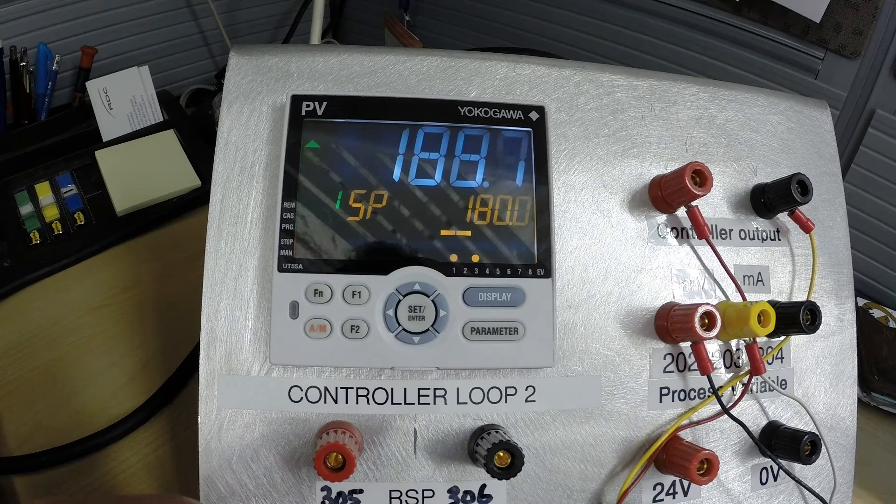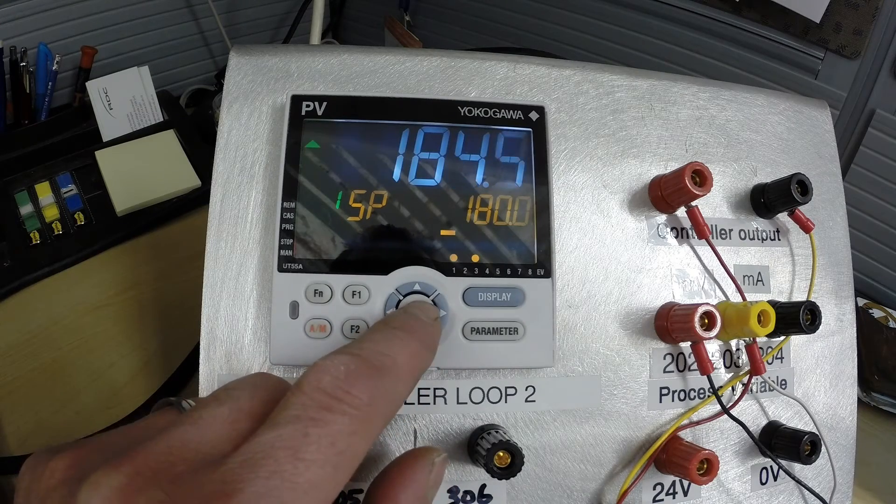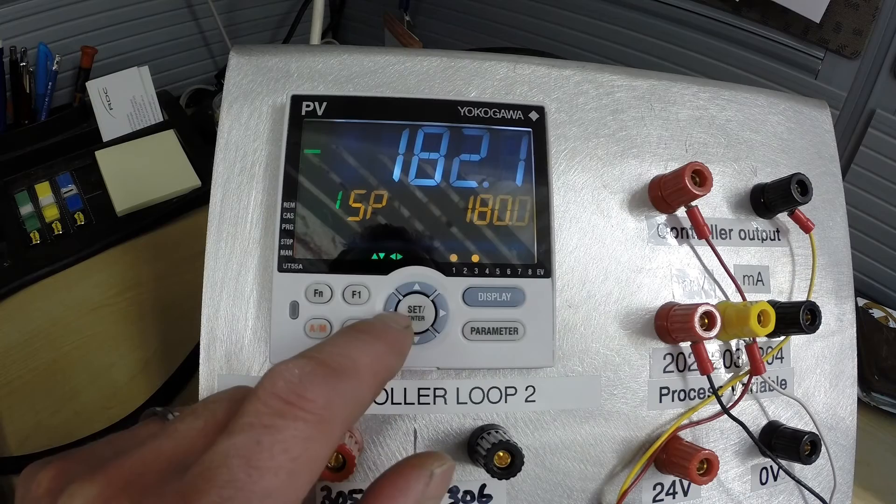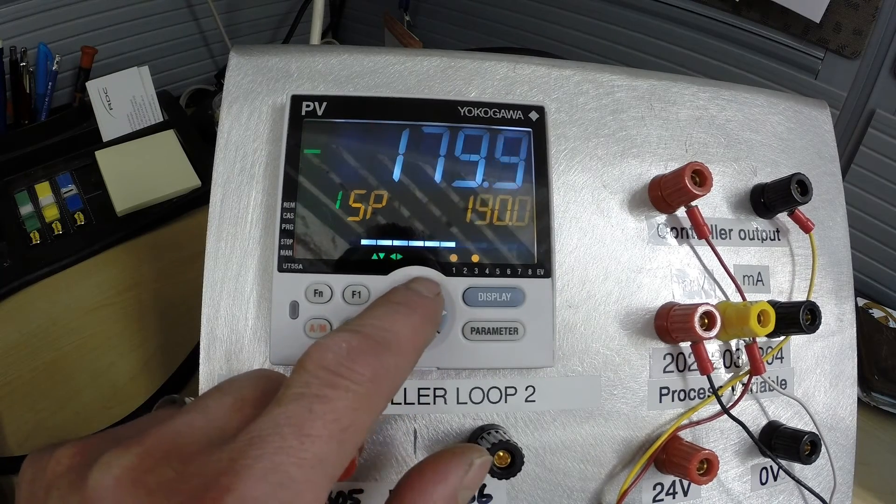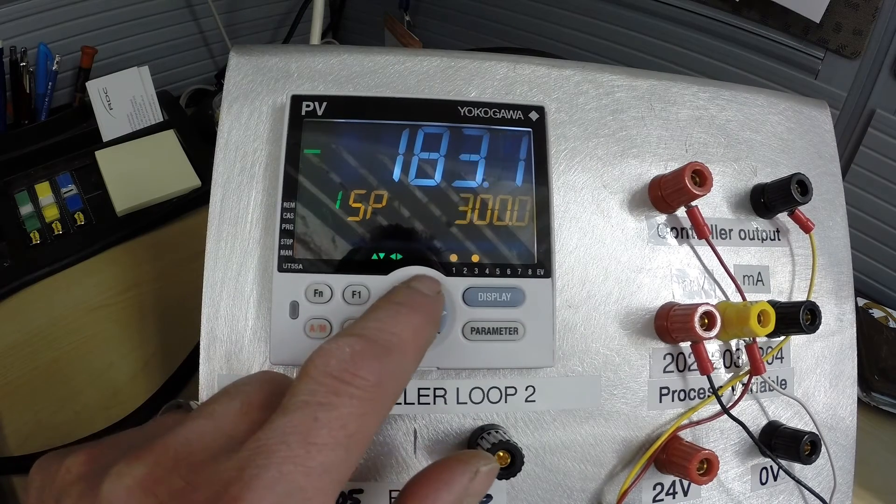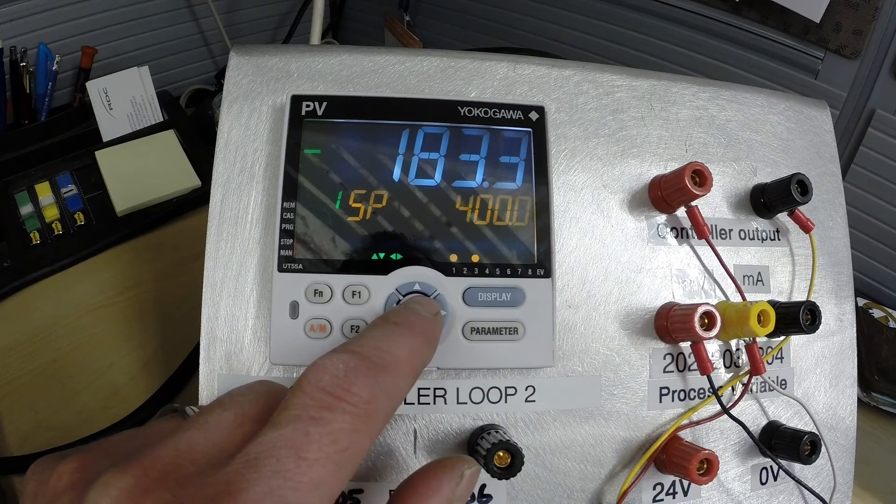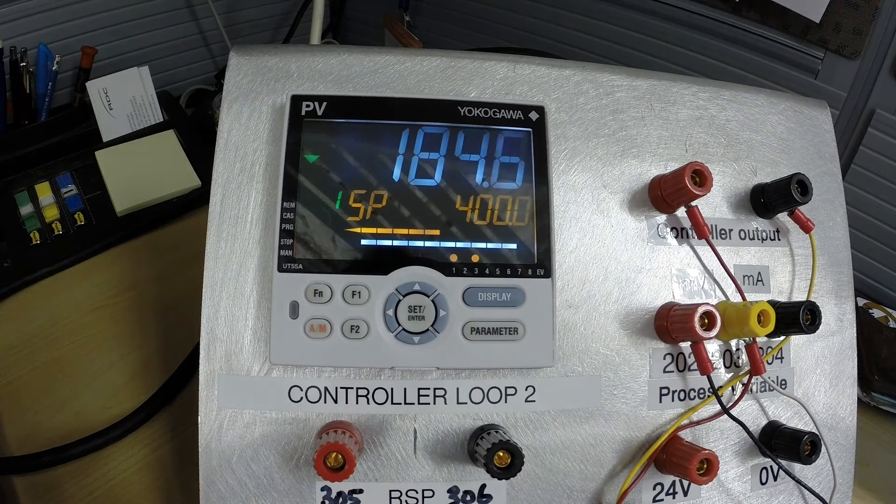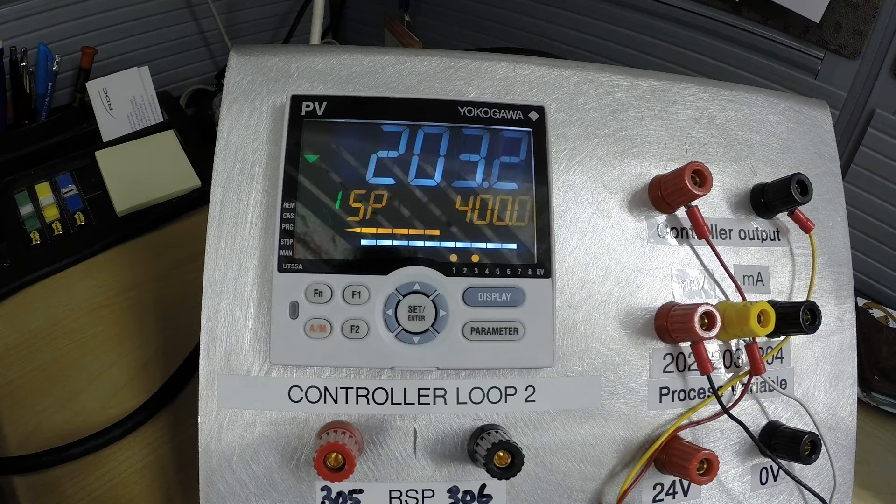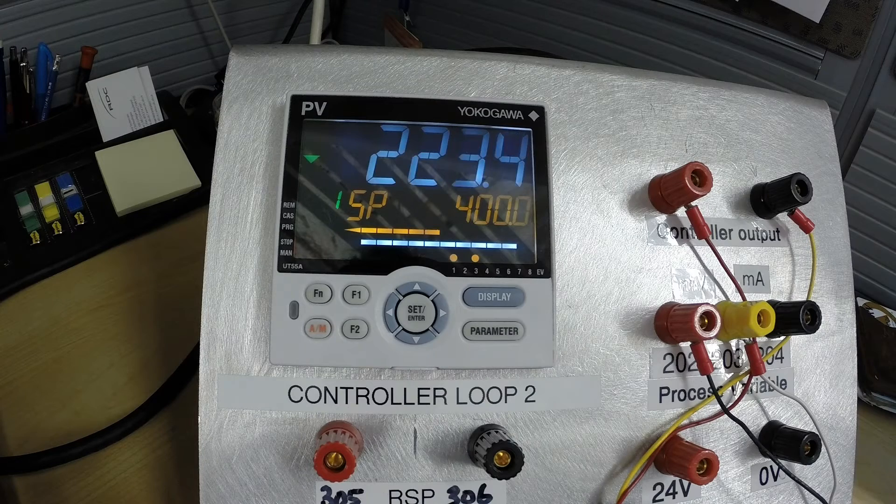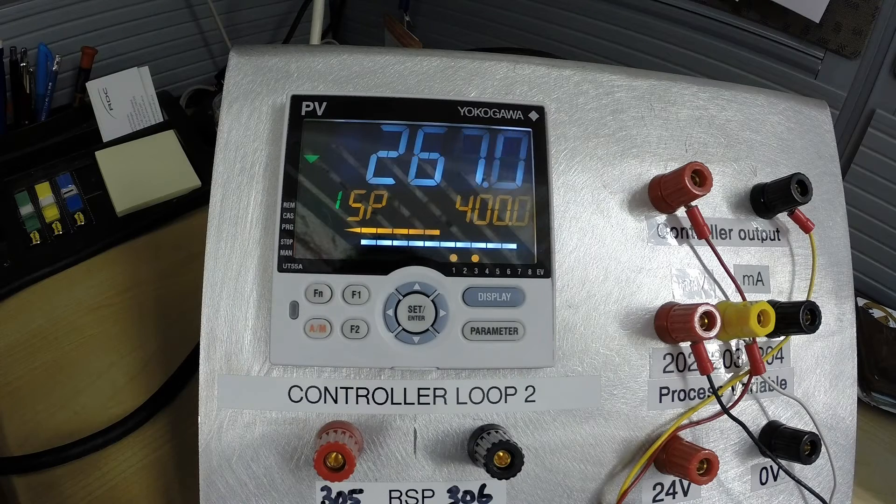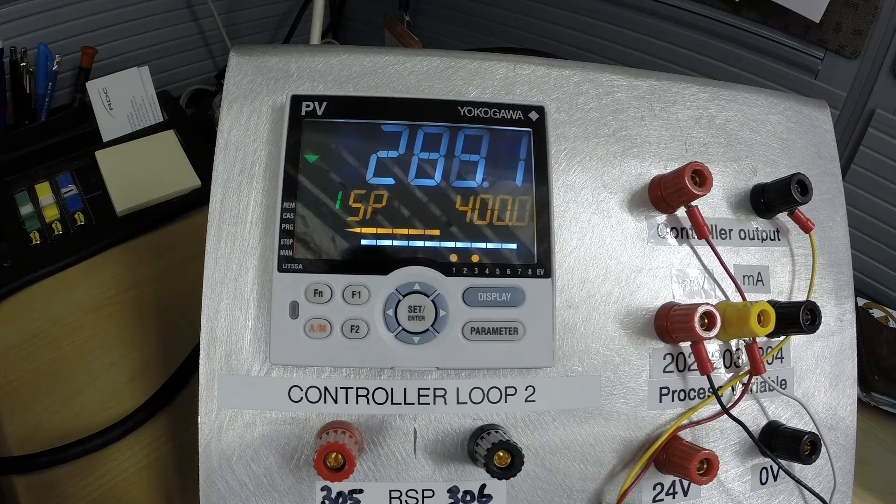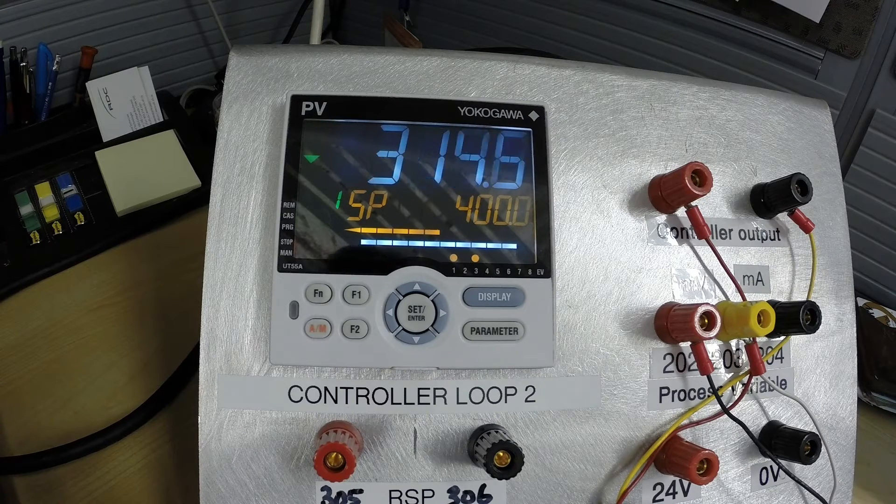Now we can exit by pressing the display button. And we can see now that it is reacting a little bit faster than it was when we initially started. We can test that by changing our set point. So let's change our set point to something like 400 degrees. So there is 200, 300, 400 and as soon as I press set you will see that the controller is going to respond to the set point change. So you see now it is quickly rising with our proportional set at 0.1. And if you do the math, 100 over 0.1 gives us a very large gain.